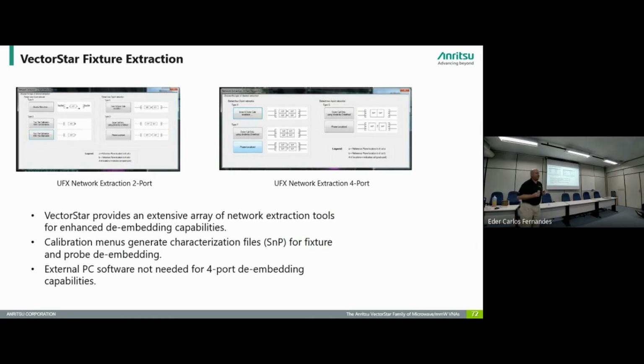For that, all I need is a 1-port calibration at the end of the cable, open short load, save that, get your connector, just the connector by itself, add it onto the cable, and measure it when it's open using UFX network extraction. Once that measurement is done, that open is measured, you will get an S2P file.